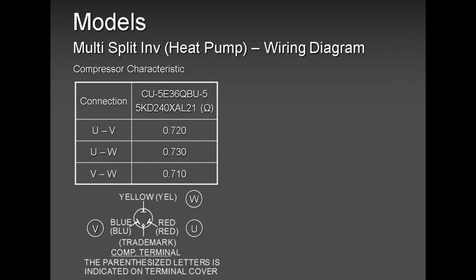There is only cross-wiring in cool mode, and that's because the coil tends to freeze because the wrong unit is running and the refrigerant is going to the wrong unit. So one indoor unit fan is blowing and the other one is freezing. And to stop it from freezing, we have an error code of F17. Once in a while, it will throw you an H39. The moment you have those two error codes, you don't have to call me, my friend. It's crossed wires. And you can swear on all your gods, my friend, but I'll tell you, you crossed those wires. And you don't have to be ashamed. It happens to anyone. 5 years in the business, 10 years in the business, 40 years in the business.